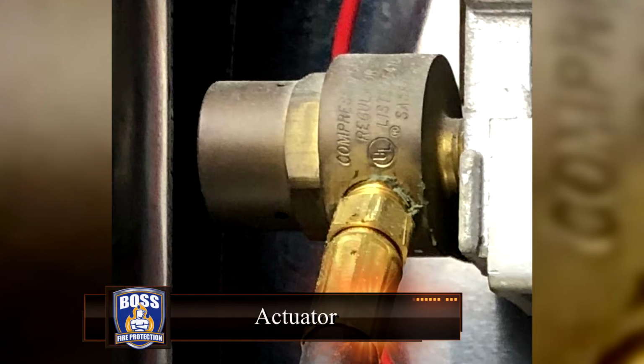The actuator regulates the compressed air that runs to the control head in the event of a fire. Hoses distribute the compressed air from the actuator to the bottles. The compressed air then pressurizes the bottles containing the wet chemical agent. This helps regulate the flow of the wet agent through the system for proper discharge. The hoses should be tested every 12 years or replaced.